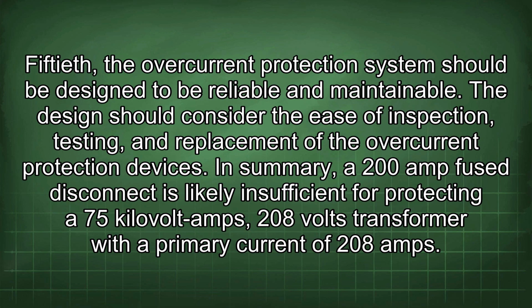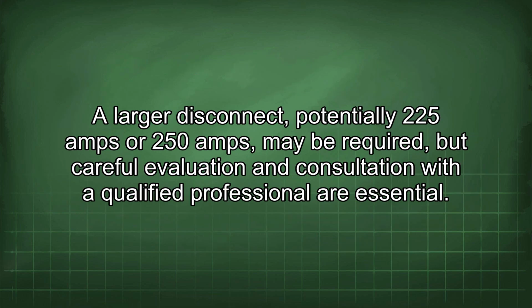In summary, a 200 amp fuse disconnect is likely insufficient for protecting a 75 kVA 208 volts transformer with a primary current of 208 amps. A larger disconnect, potentially 225 amps or 250 amps, may be required, but careful evaluation and consultation with a qualified professional are essential.